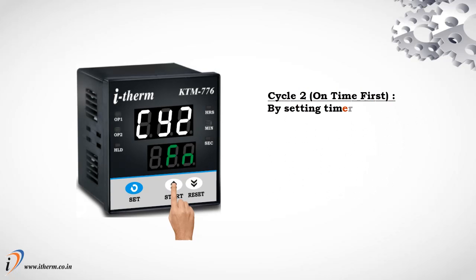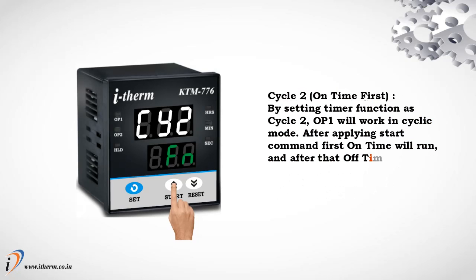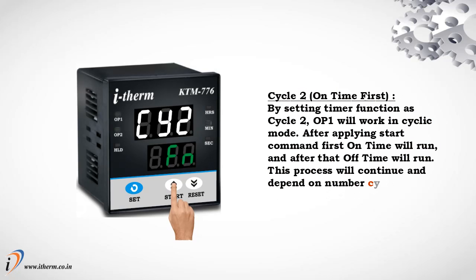Cycle 2 — on time first. By setting timer function as Cycle 2, Output 1 will work in cyclic mode. After applying start command, first the on time will run, and after that the off time will run. This process will continue depending on the number of cycles parameter in the user list.